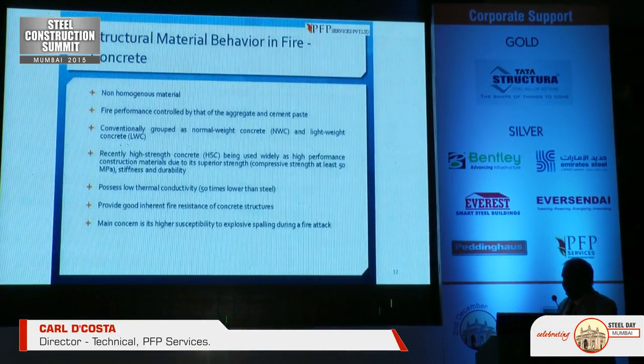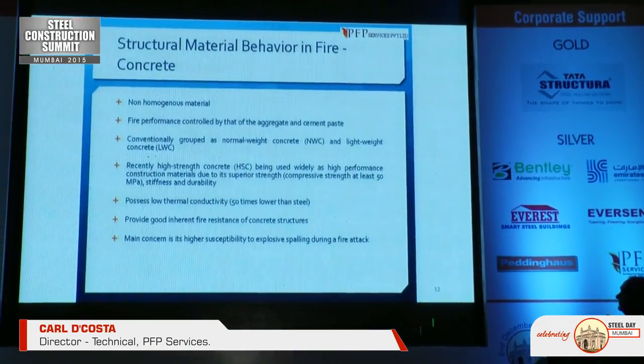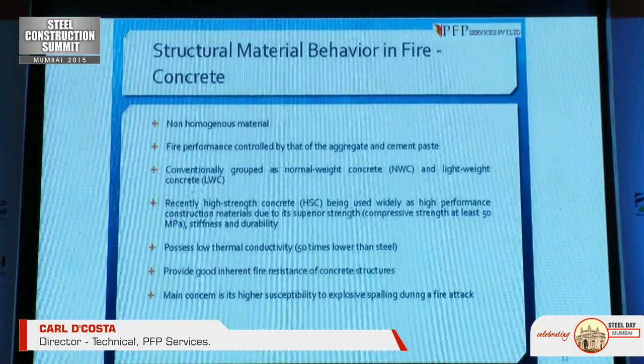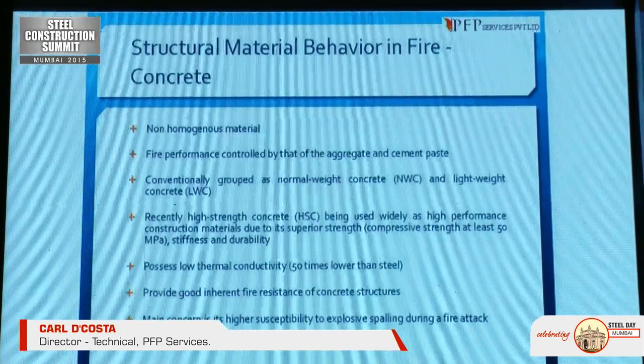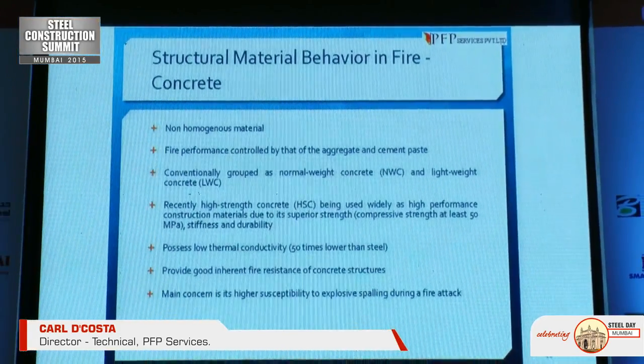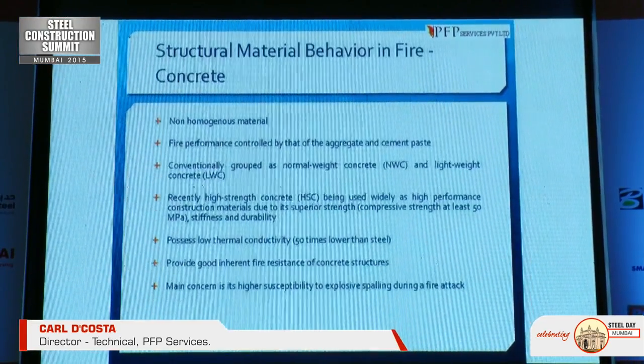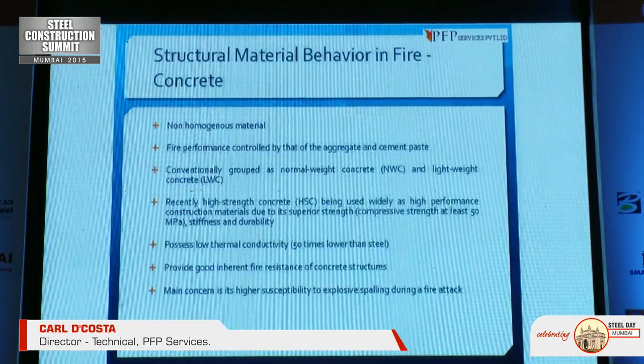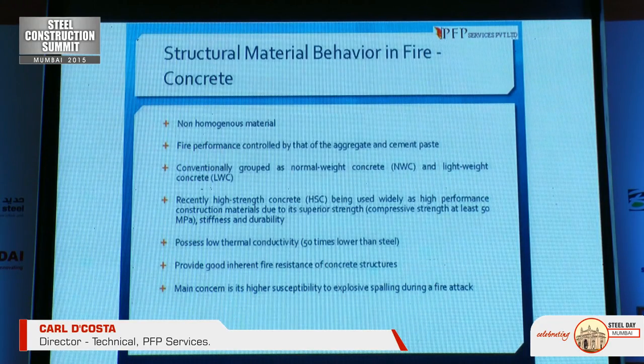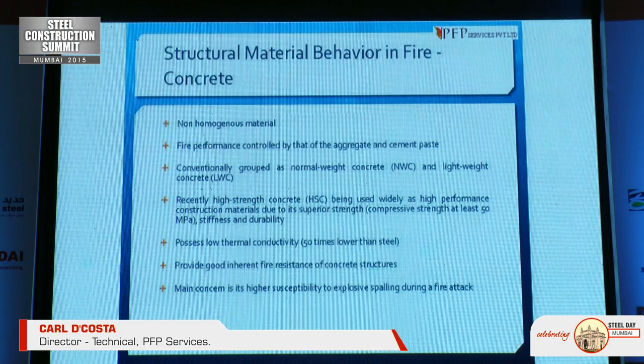The types of fireproofing materials: one is concrete. It is non-homogeneous, and its fire performance is controlled by that of the aggregate and the cement paste. Conventionally grouped as normal weight and lightweight concrete. High-strength concrete has been widely used due to its superior compressive strength of at least 50 MPa, stiffness, and durability. It possesses low thermal conductivity — 50 times lower than steel — providing good inherent fire resistance. However, the main concern is its high susceptibility to explosive spalling during a fire, especially when the fire brigade applies hoses.